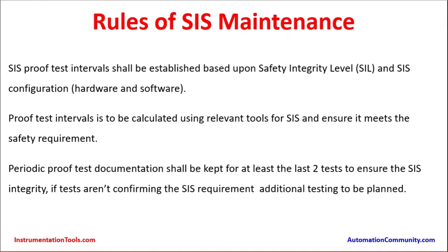SIS proof test intervals shall be established based on Safety Integrity Level (SIL) and SIS configuration — hardware and software. This covers configurations such as 1oo1, 1oo2, 2oo2, and 2oo3. Proof test intervals are arrived at based on the SIL, calculated by safety system experts. Proof test intervals are to be calculated using relevant tools and must ensure the safety requirements are met. Different tools are available from international agencies for these SIL calculations.